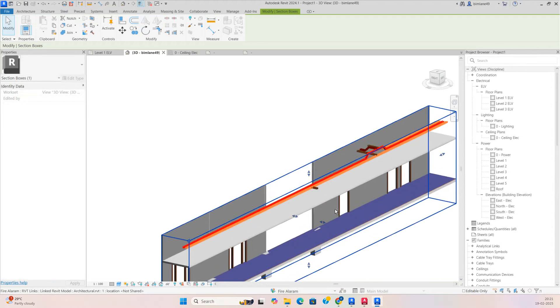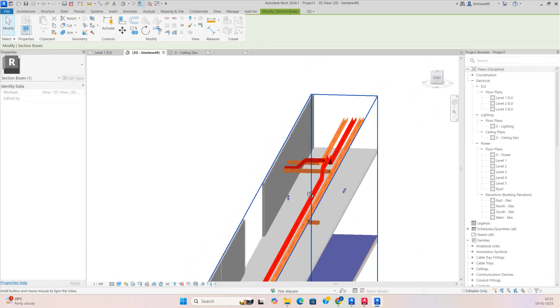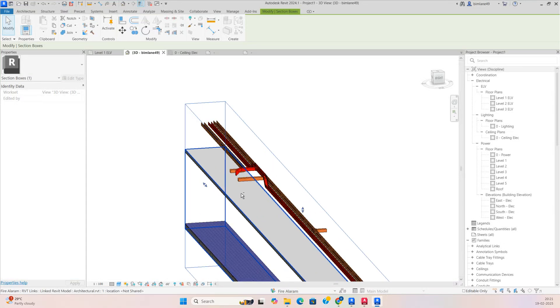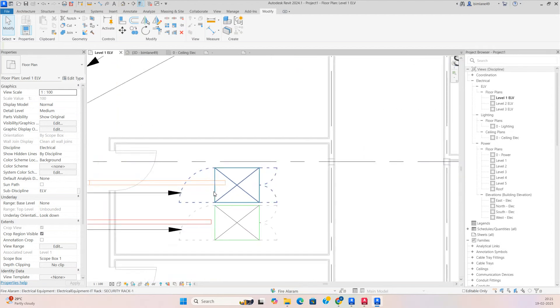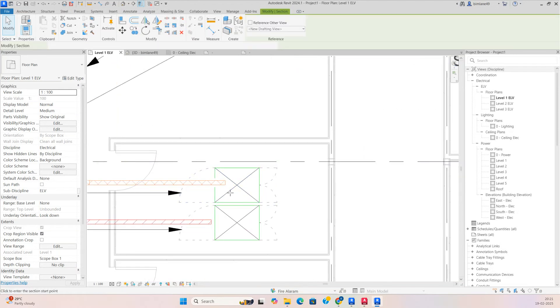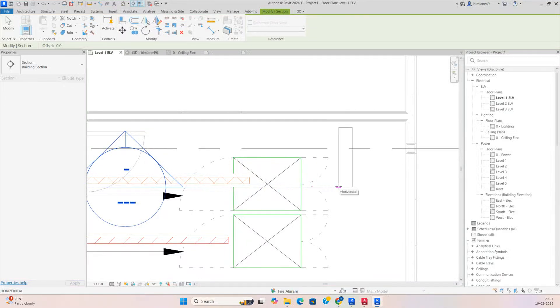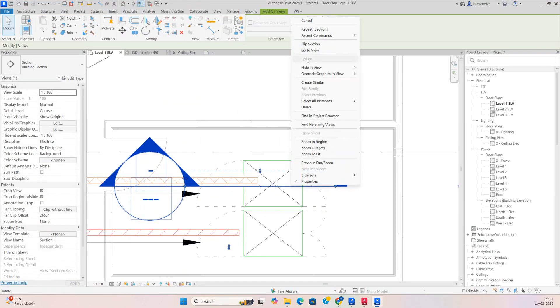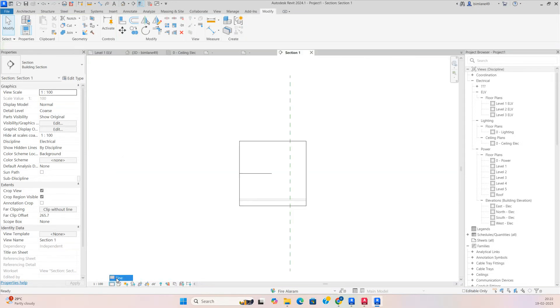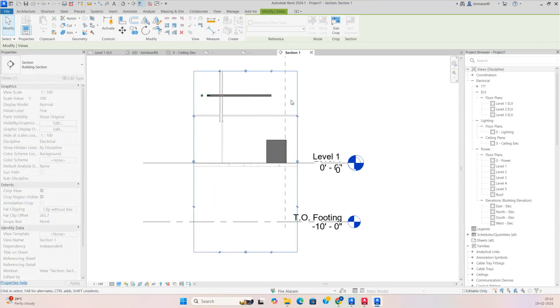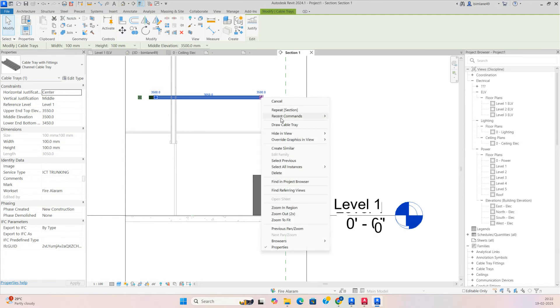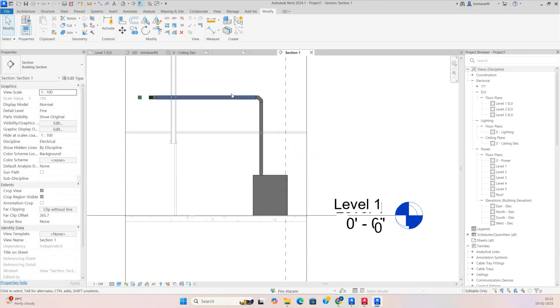You can go to the 3D view and look at how the cable trays look, how to make the bends, and everything. One important thing: how to drop the cable tray to the panel. Make a section over here, go to View, give it a fine shaded display, and then you can draw the cable tray down to the panel by selecting Draw Cable Tray. This is ICT Trunking dropped to the panel.